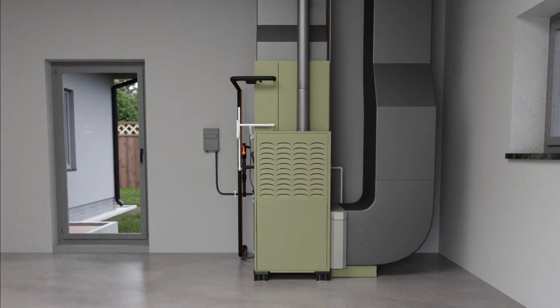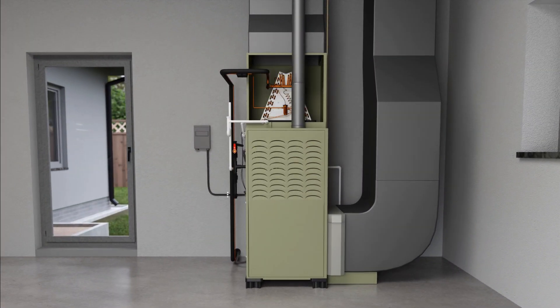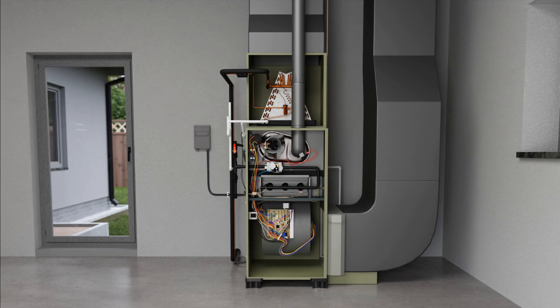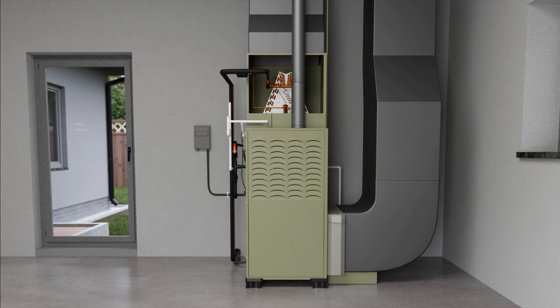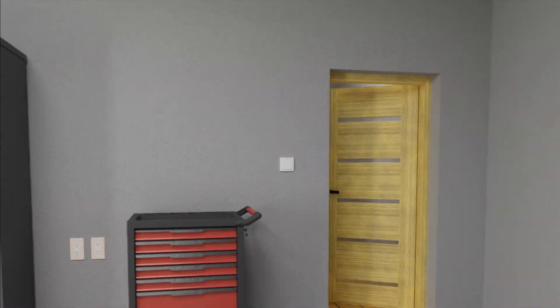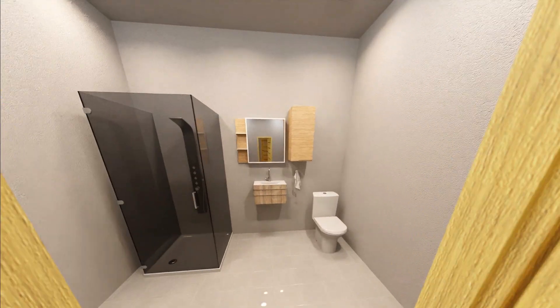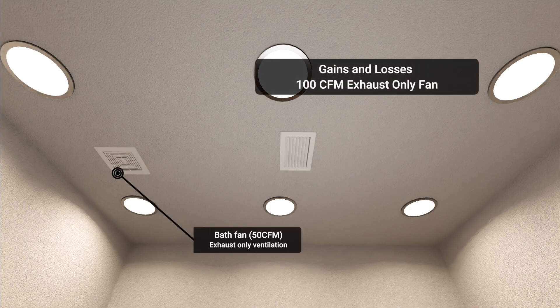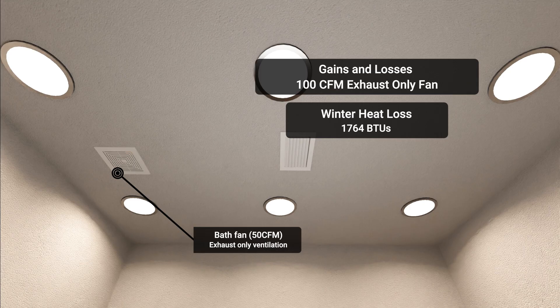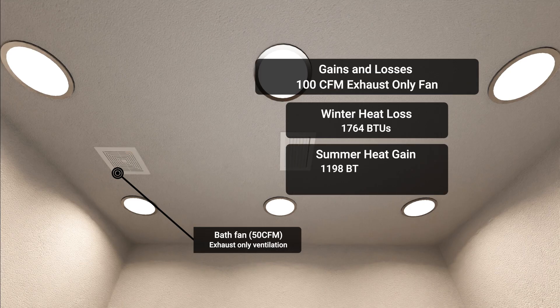We also need to know if the air handler or furnace is in a conditioned space or an unconditioned space. In many cases the air handler is in a garage or an attic, which are usually unconditioned spaces, but air handlers may also be in closets within conditioned spaces. In this example, 100 CFM of exhaust-only ventilation would be responsible for 1,764 BTUs of heat loss in the winter. In the summer, we can expect infiltration to be responsible for 1,198 sensible and 2,004 latent BTUs of heat gain.